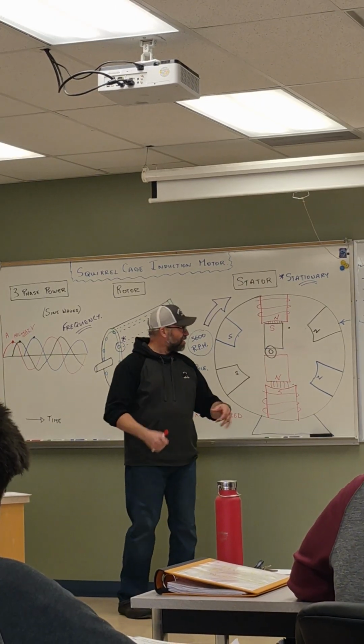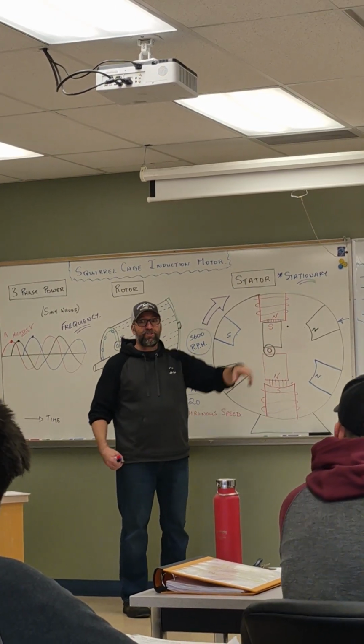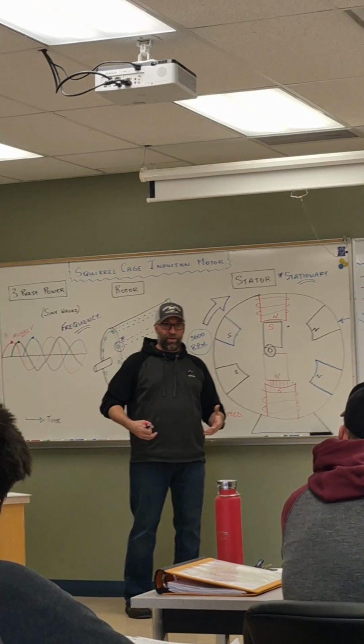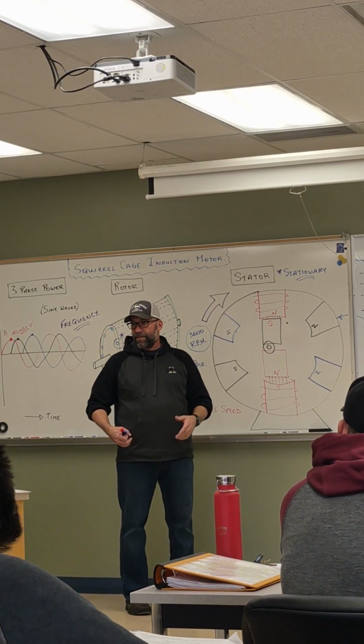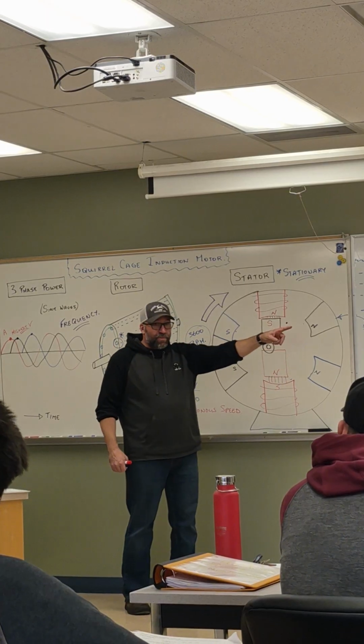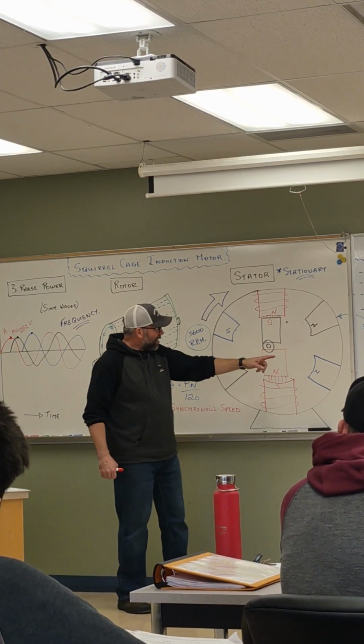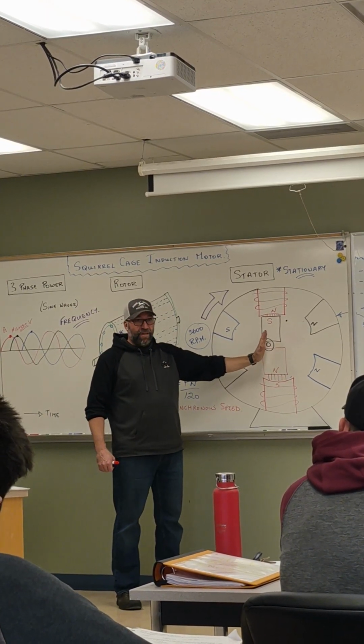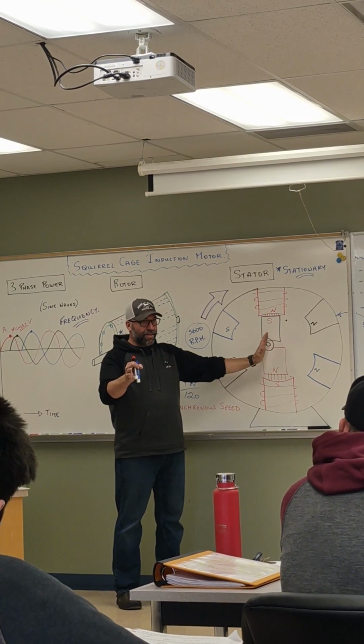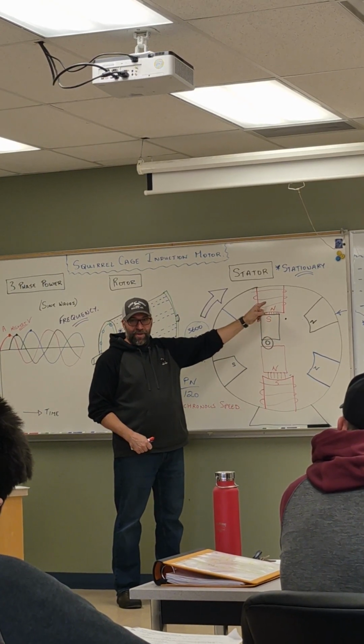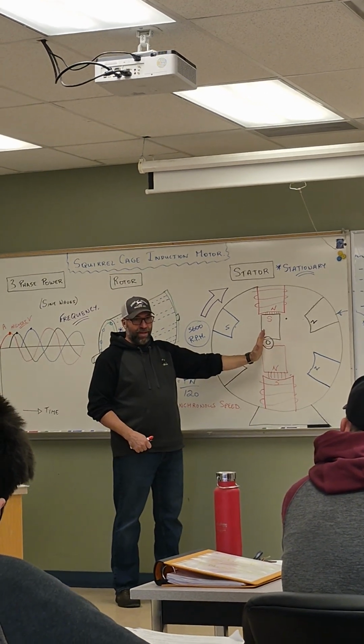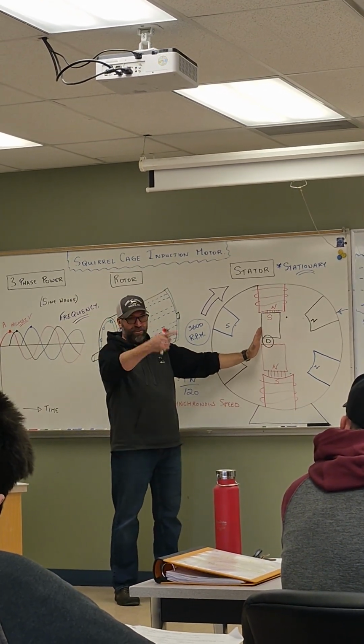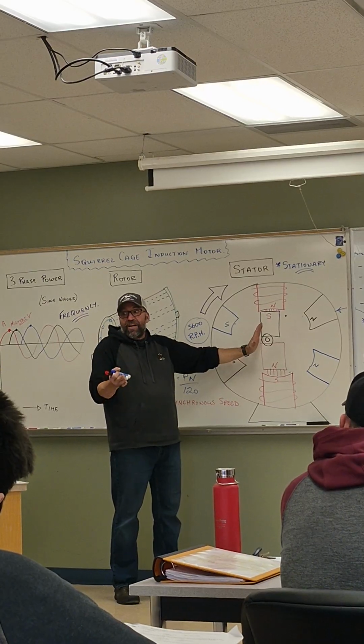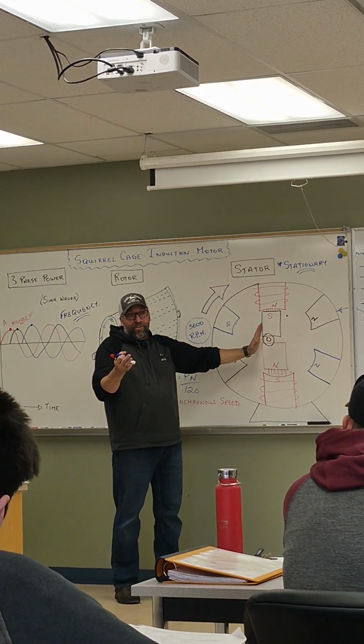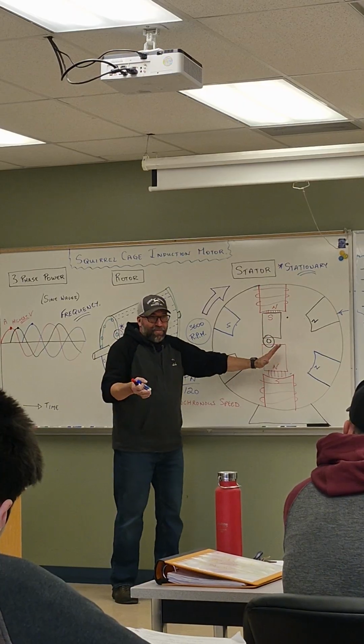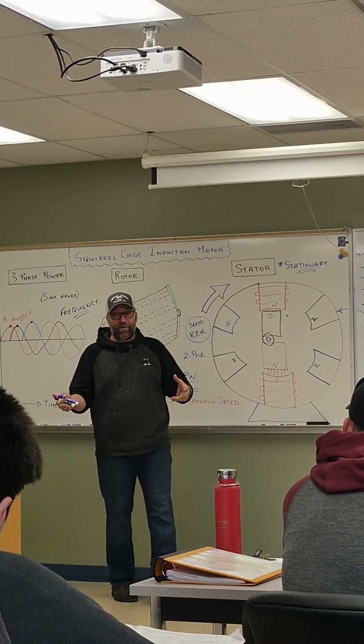And when that happens, these little motor windings, those little rotor bars, they're trying to carry the weight. They're trying to actually do the work. They can't, they'll burn out. So the whole reason that those little tiny rotor bars are there in the first place is if I turned on this magnet in the middle, and then I instantly turned on this magnet going 3,600 RPM, this will never catch up. It's trying to catch up, that's going way too fast around the outside. So we have to get it close, so that when we turn this on, it just has to move a bit, and once it locks on, it's almost the same speed anyways.